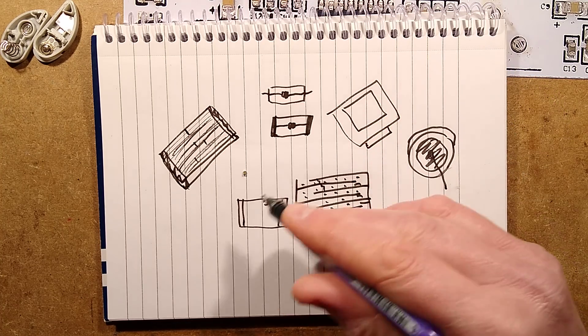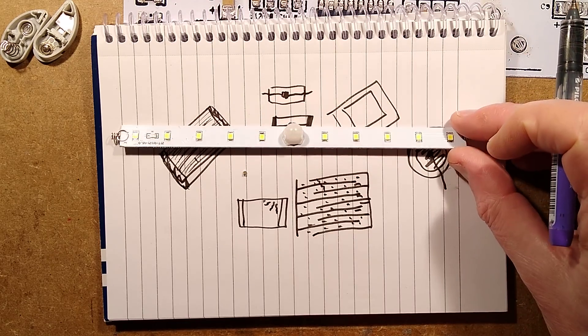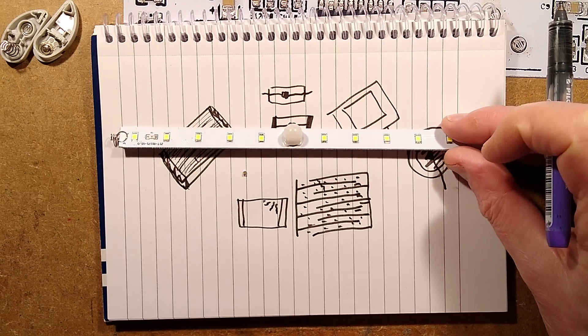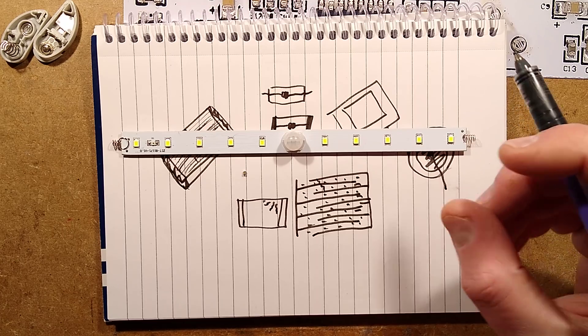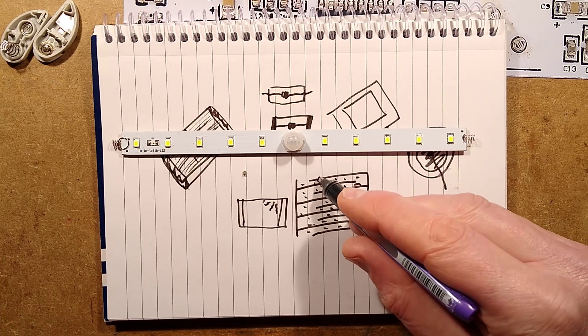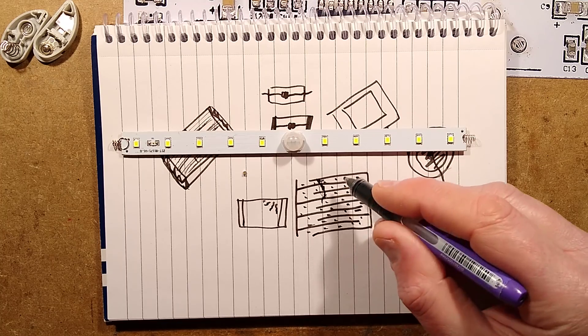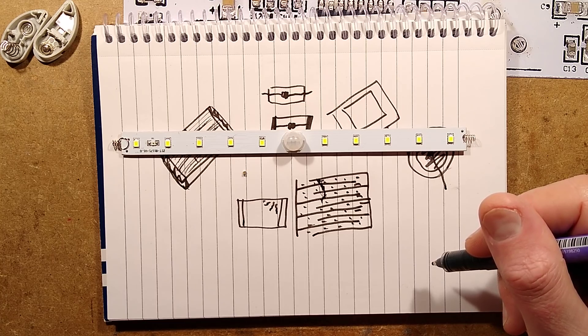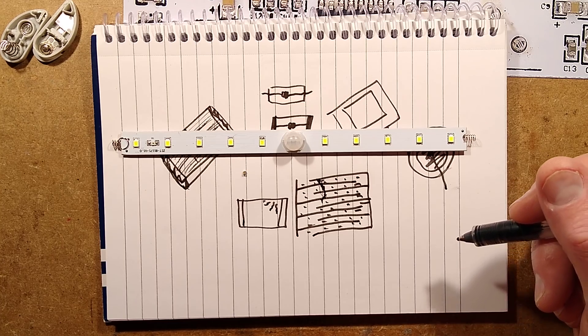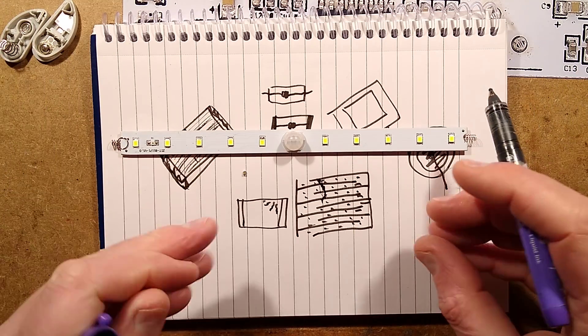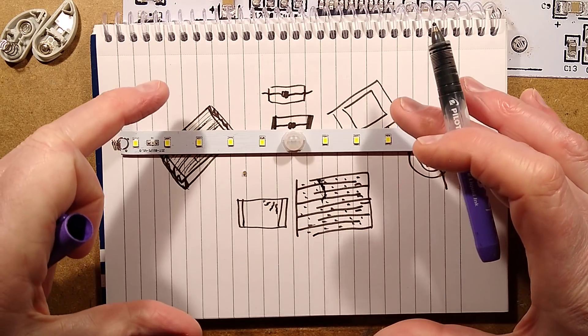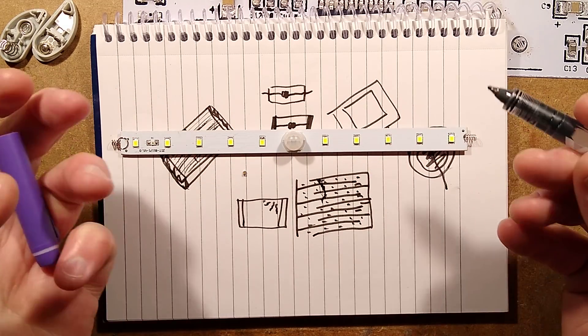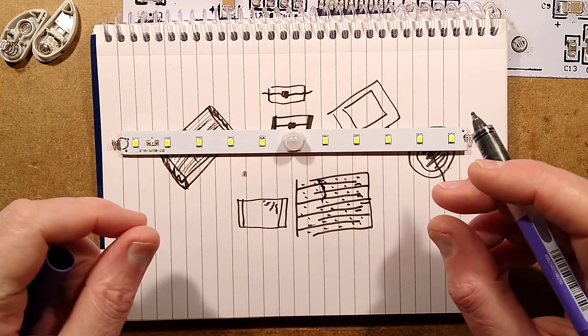Because it failed and its resistance at the heat then caused it to fracture further and break down, and it started just burning between the conductive layers. And he had quite a little inferno in his hands there because it was just bridging between the low voltage DC supply, but it was shorting that out and acting like a resistor. And this is a common problem. This isn't the first passive infrared detector that I've come across that's had that same problem, that it's been running batteries flat because the main input smoothing capacitor was just displaying a resistive characteristic that had fractured, moisture had got in, and it basically had gone conductive.